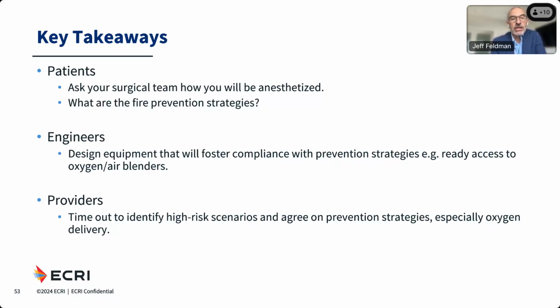And engineers, you can design equipment to foster compliance with prevention strategies, in particular, ready access to oxygen air blenders. And for providers, that timeout scenario really needs to be taken seriously, where the team recognizes the risk, agrees on prevention strategies, particularly oxygen delivery, and then follows those strategies. And if all those things are done, these fires will go away. They are 100% preventable.